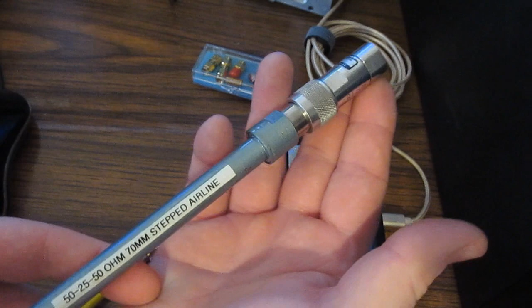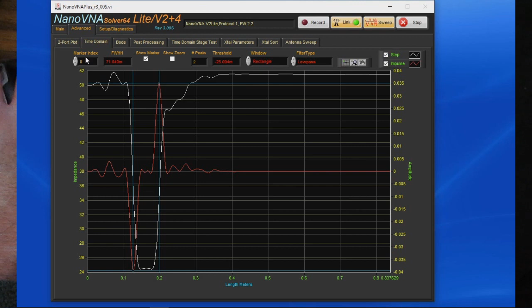And here's our cursors. You can see these are off quite a bit. What we can do is select the cursor marker. We'll pull this down slightly, maybe into this area here. This will set the trigger level. You can see the two cursors are now located at the apex of the impulse wave. And as you can see, the full width half height is measuring roughly 71 millimeters.